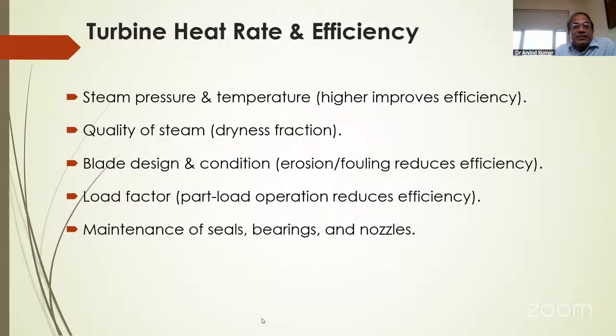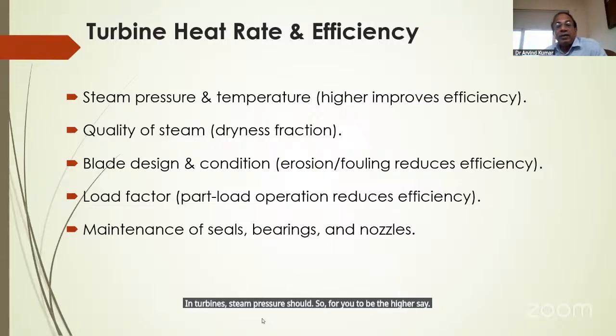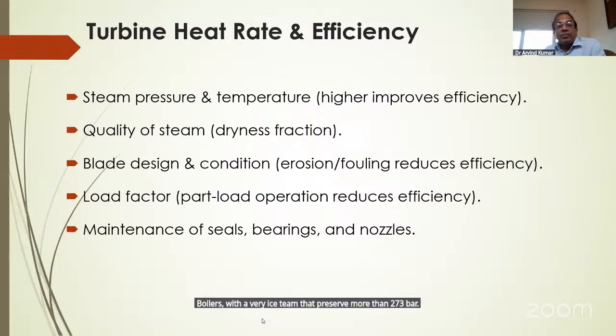Turbine heat rate and efficiency, steam pressure and temperature. In turbines, steam pressure is supposed to be on the higher side, and we are going for supercritical boilers, where the steam pressure is very high, more than 273 bar. So the efficiency of the steam turbine is very high. At higher pressure, the efficiency is higher.